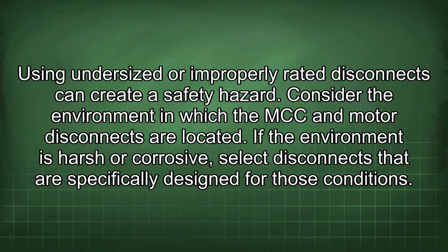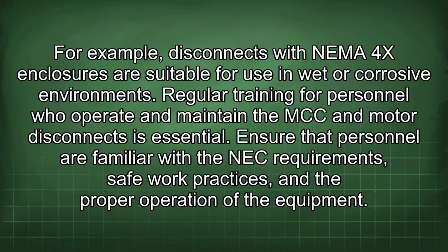Consider the environment in which the MCC and motor disconnects are located. If the environment is harsh or corrosive, select disconnects that are specifically designed for those conditions. For example, disconnects with NEMA 4X enclosures are suitable for use in wet or corrosive environments. Regular training for personnel who operate and maintain the MCC and motor disconnects is essential. Ensure that personnel are familiar with the NEC requirements, safe work practices, and the proper operation of the equipment.